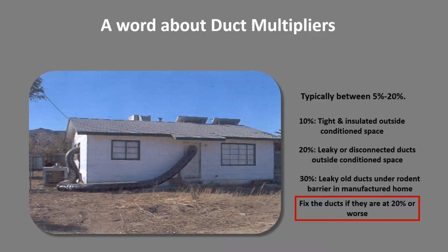Typically, it's between 5 and 10%, and the duct multiplier is the penalty anytime you put the ductwork outside the house, either in the attic or the crawl space, sometimes the garage. 10% is about as good as you can get. That's well insulated and almost airtight. 20% is sort of normal. And if it's 30% or higher, you really should consider fixing the duct system. It's hard to make people comfortable with a bad duct system that delivers warmer air than expected in the summer and cooler air than expected in the winter.